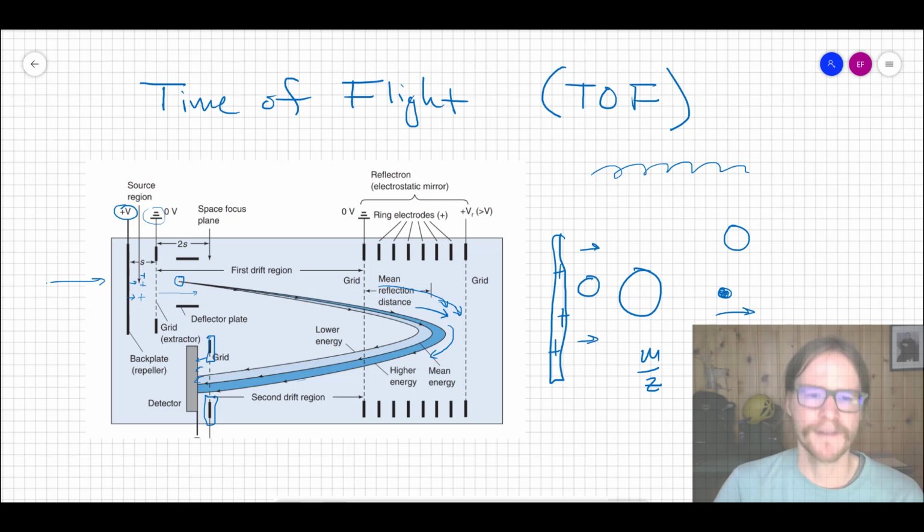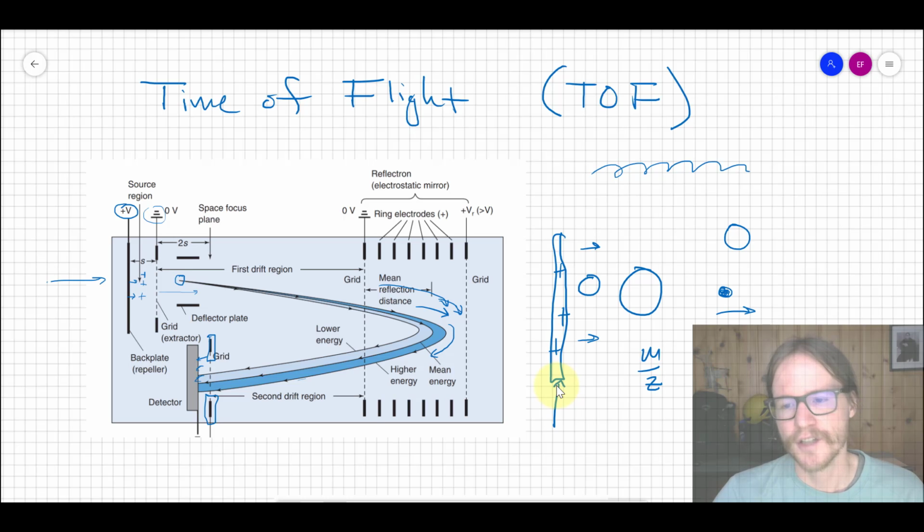The problem with time of flight instruments is they're based on the fact that because you're applying the same voltage to all the ions, the kinetic energy of all these ions is the same, at least as it enters here. And the separation then is based on, if kinetic energy is 1/2 mv squared, then the separation occurs based on the differences in the mass here. But it's difficult to impart exactly equivalent kinetic energies to all these ions. They can collide with each other, and so what happens is the resolving power, that delta mass to charge, the ability to differentiate, is lower typically than a quadrupole.